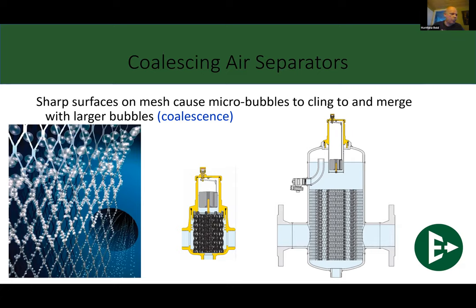And I mean extremely. I mentioned a couple of slides ago, Mother Nature loves balance. And with regards to water, the water in its natural form carries high levels of oxygen. So what we're doing in hydronics is getting that air out. If we get it out and start to pull it out of solution, we now start to pull air back into the water solution from little air pockets elsewhere in the system. Maybe you have a 90 that during the flush and fill didn't quite get that last little bit of air out of the top corner of that elbow, so the flow through that is a little bit slow. Over time, and usually it's not very long at all, about 24 hours, maybe a little bit longer depending on the case, a high efficiency air separator will pull those air pockets out of a system.